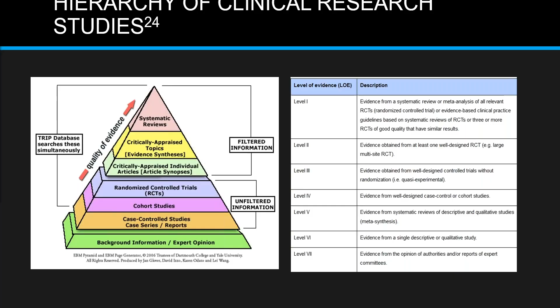First, we have to demonstrate the efficacy and effectiveness of a disinfectant or device for disinfection. Efficacy means a study that's done under ideal circumstances. In a clinical trial, that's a randomized clinical trial. Effectiveness means how does it work in real life situations? So we want to demonstrate that a disinfectant or a device inactivates microbes that you would inoculate onto a surface of medical devices. Then the key thing for the disinfectant or the device is the antimicrobial spectrum. What does it kill? Obviously, for vaginal and rectal probes, it must disinfect things such as gonorrhea, syphilis, HIV, sexually transmitted agents, but certainly also HPV.